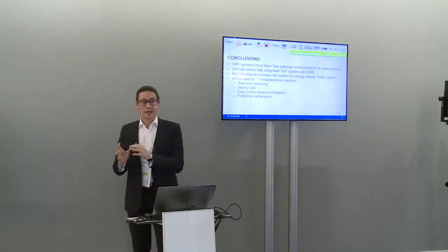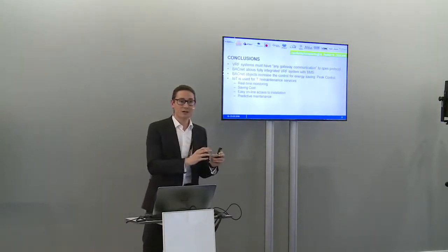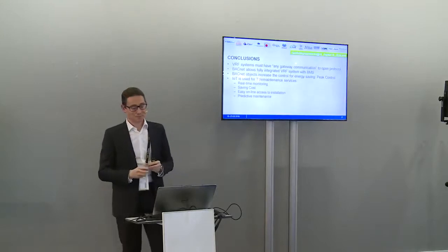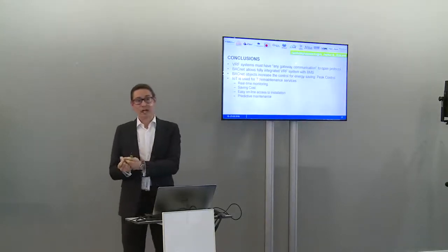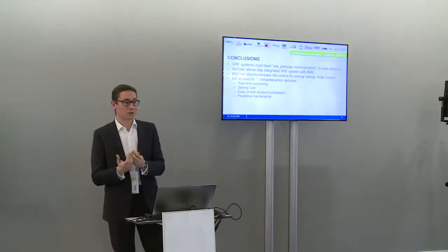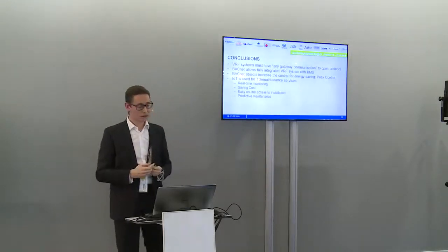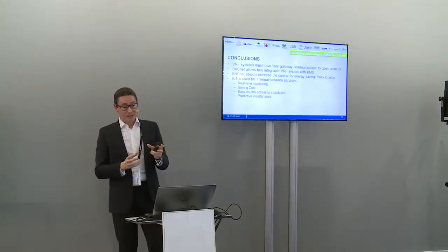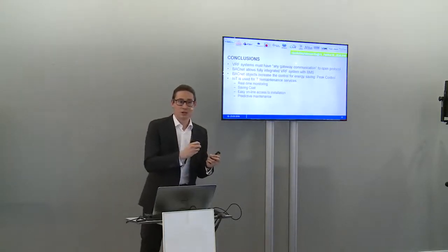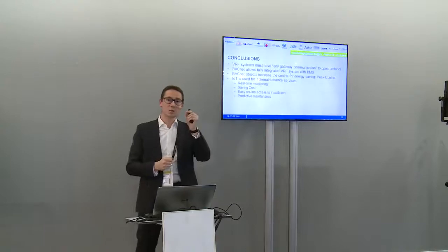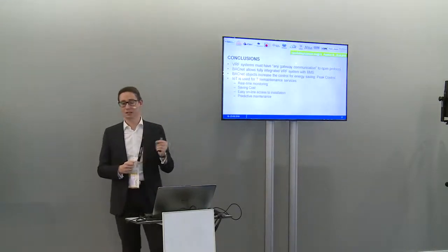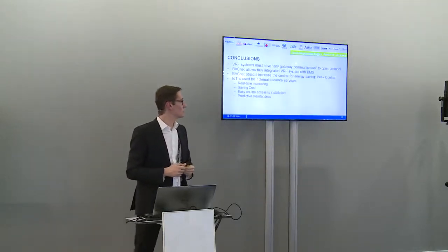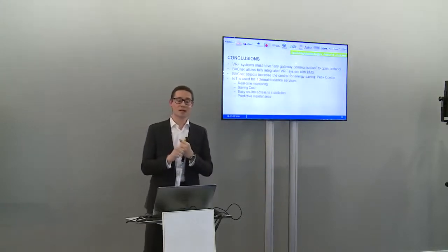So as a conclusion, in the opinion of LG Electronics, all the VRF systems need to have a gateway for the standard protocol. Also, communication with the BMS is really important, maybe DDC or BMS solution, it doesn't matter, but an open way of communication. Obviously, we have the peak control that I mentioned before. It also works in small pieces to save a little bit of money in energy or power consumption in the installation. And finally, the IoT solution used for telemaintenance can save cost.